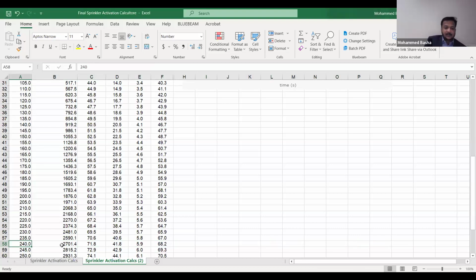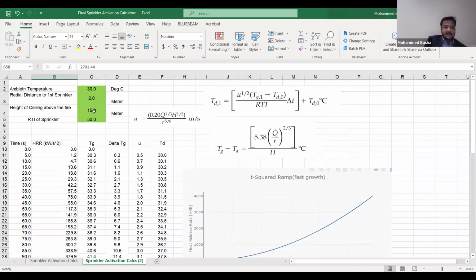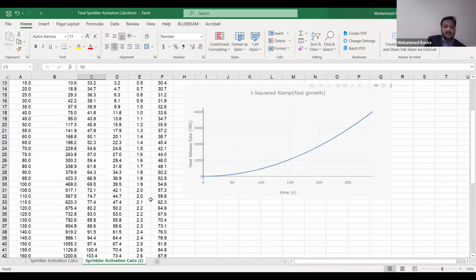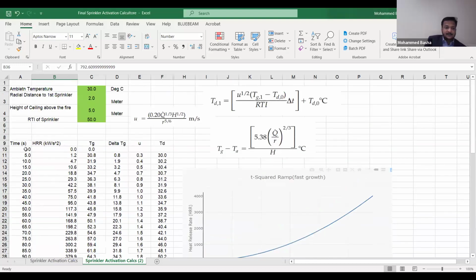Then what is the heat release rate of the fire at that time? 2.7 megawatt. This is the Q value you need to consider. Now, if the ceiling height is changed to 5 meters, of course, the value will be reduced. The sprinklers will be activated at 130 seconds itself. The HRR at the time of sprinkler activation is 792 kilowatt, which is 0.7 megawatt, considerably less than the previous example. So in this way, you can change these values.